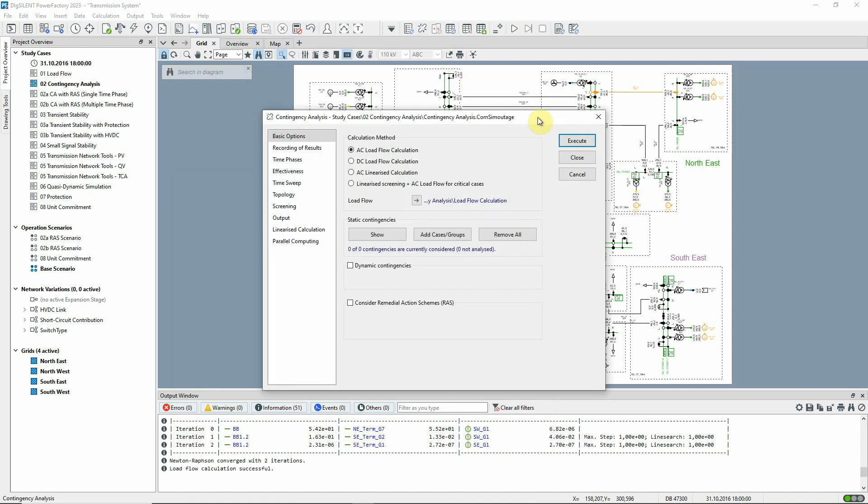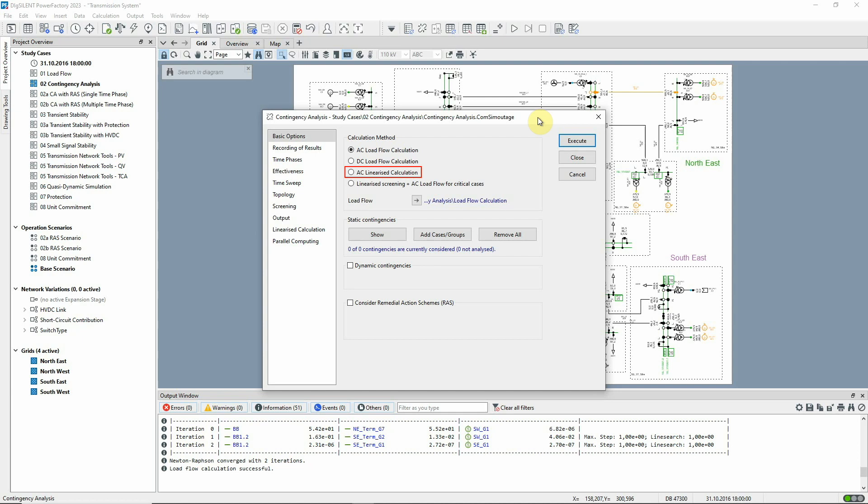There are three main calculation methods. The first is a calculation using a full AC load flow. The second is a faster DC calculation, which calculates active power but uses nominal voltages. The third is an AC analysis method that represents the contingency case by using equivalent injections to reduce the flow through the faulted area to zero.